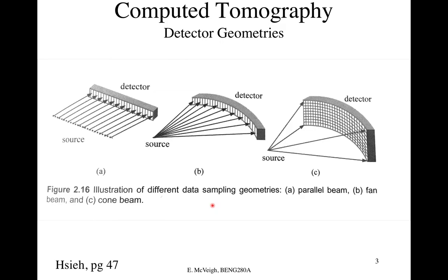So we don't raster a single detector anymore. We have a fixed set of detectors, in fact a two-dimensional fixed set of detectors. So it's just like a camera. We're going to click and take a picture that way. And the separation between these elements kind of sets our sampling frequency in the l direction with g(l, theta). So that's already set for us by the manufacturer. Unfortunately, we can't dial it and shift them down, shift them up.